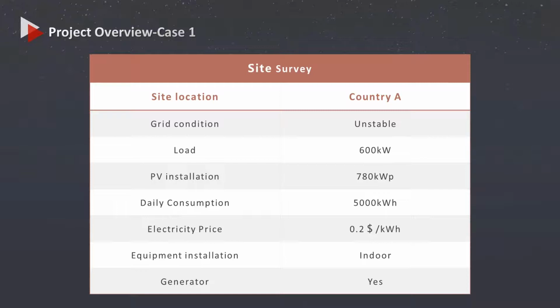Then, to maximize use of the factory building's roof area, the customer determined the PV capacity to be 780 kilowatts, so we chose 3 PBD250 units. Finally, we calculated the excess power based on the customer's usual load consumption, charging that excess into the battery, resulting in a battery capacity of about 730 kilowatt hours.